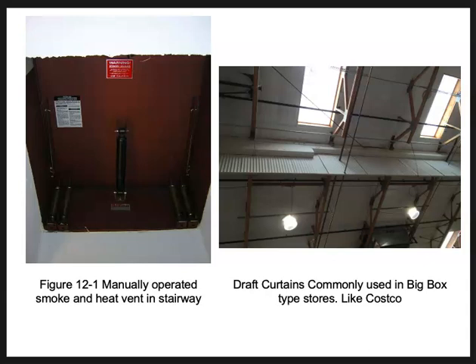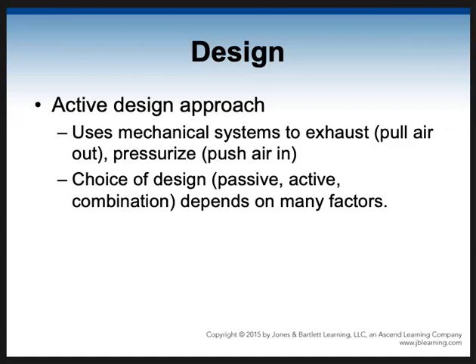Others are made with a kind of plastic that rates at a certain heat, and that are rated to melt at a certain heat. So when the heat builds up, they start to drip, and eventually they melt, and it allows the smoke to passively leave the building. So these are examples of passive smoke protection.